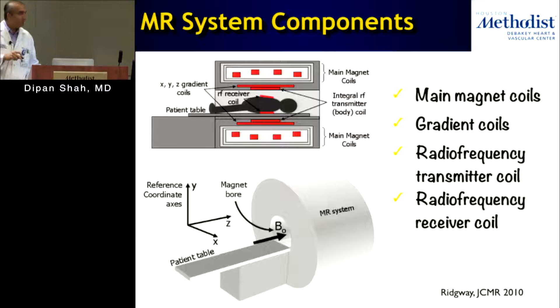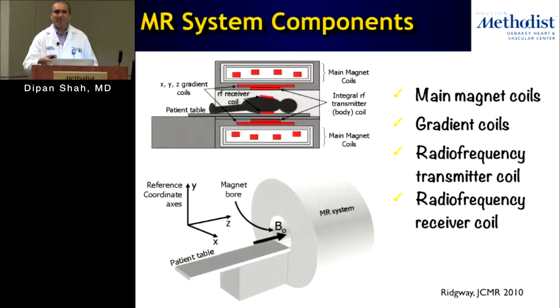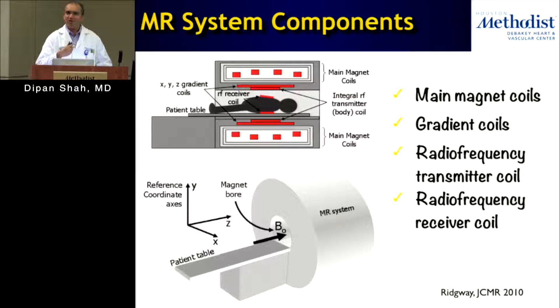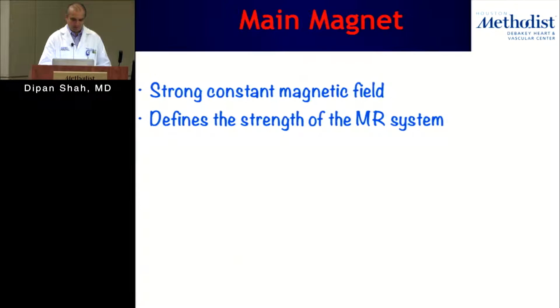The receiver coils can be within the bore or within the magnet itself, and there are also receiver coils we place on the patient. If you've seen or had an MRI scan done, you'll notice you get some coils placed on top of you. Those are receiver coils designed to be placed very close to the object being imaged, to help improve image resolution and image quality.